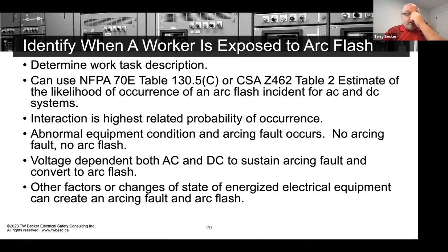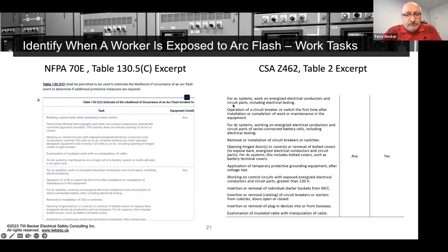So voltage dependent, what's my work task? What's the maximum nominal voltage that I'll perform it at? And will that be an electric shock hazard for me? In this case, sustain an abnormal arcing fault and arc flash. So here's just some excerpts of the tables just to show you. You can go to these tables in 70E. I call these standards toolboxes. Take the tools out of the box, interpret them. Don't just accept them, interpret them, maybe modify them, and then train your workers on that specific information, modification or your interpretation, above and beyond any generic arc flash and shock training.